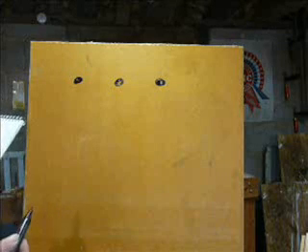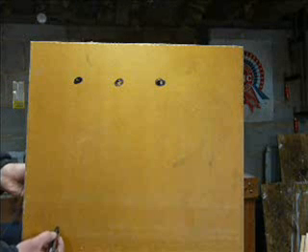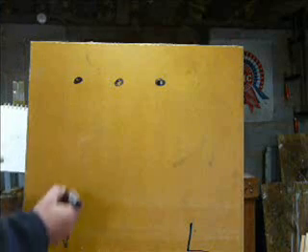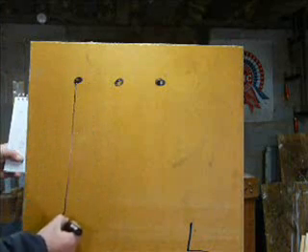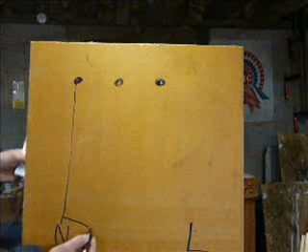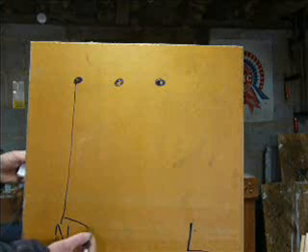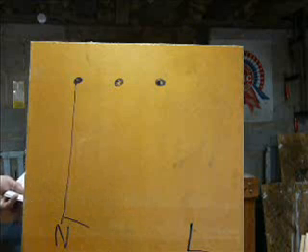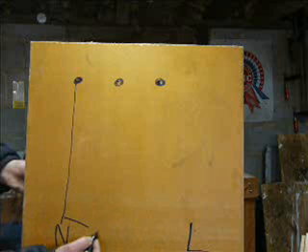Thanks for that — I was just being pragmatic at the time. So what we've got here is a neutral and a line coming in. Neutral goes straight through to one of the motor connections, but also off the neutral you've got the stop switch. The stop switch is normally closed, so it's on until you press it.